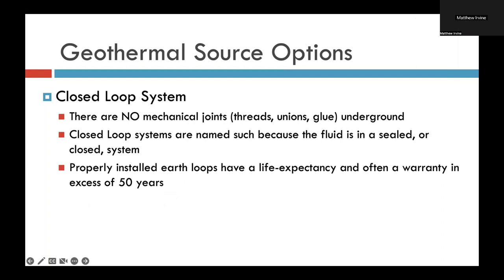So in a closed loop system, there are no mechanical joints, no threads, no unions, no glue underground. And closed loop systems are named such because the fluid is in a sealed or closed system. And properly installed earth loops have a life expectancy and often a warranty in excess of 50 years. All of the physical properties that make plastics so lousy for landfills are the exact same physical properties that make plastics so ideal for earth loops, right? It doesn't rust, it doesn't decompose, it doesn't oxidize, it doesn't otherwise break down.